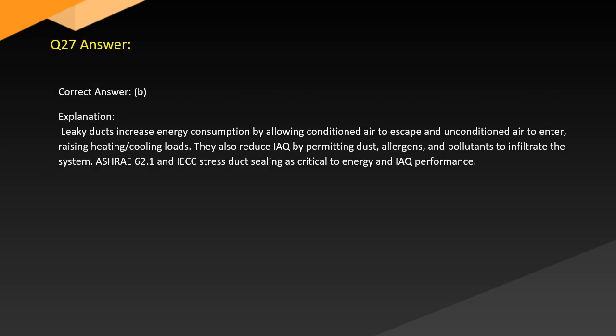Answer. Correct answer: B. Explanation. Leaky ducts increase energy consumption by allowing conditioned air to escape and unconditioned air to enter, raising heating and cooling loads. They also reduce IAQ by permitting dust, allergens, and pollutants to infiltrate the system. ASHRAE 62.1 and IECC stress duct sealing is critical to energy and IAQ performance.